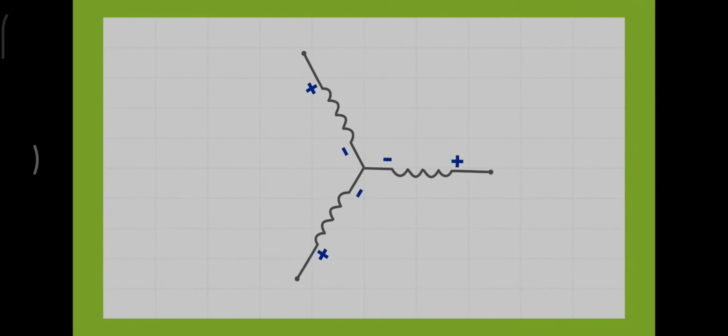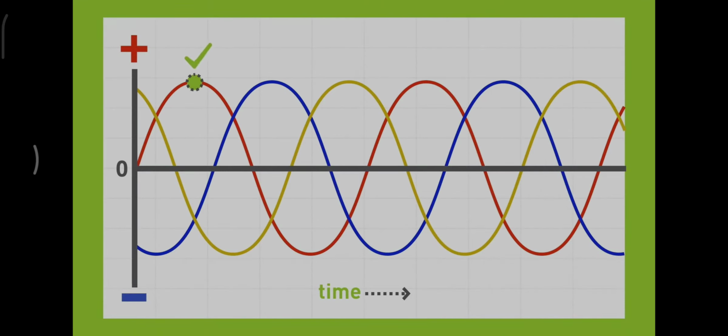As an example, let's use a three-phase 208 volt line. Each of the 3 lines will be carrying 120 volts. If you look at the chart, you can easily see the power output of any 2 lines. If one is at peak, the other line isn't at peak. That's why in a 3-phase circuit, it's incorrect to multiply 120 volts times 2 to get 240 volts.